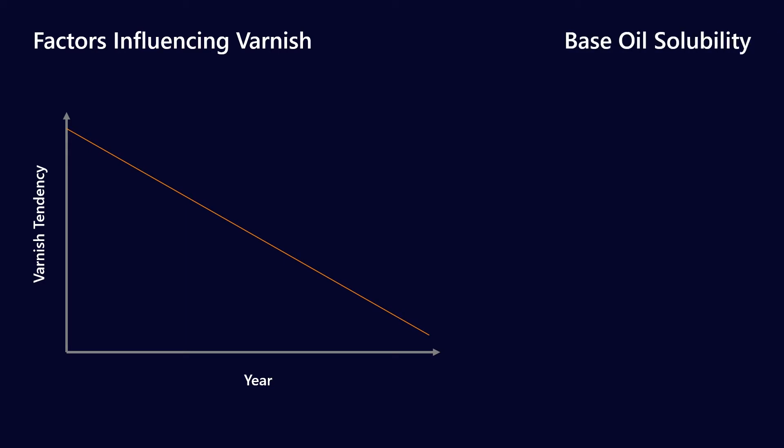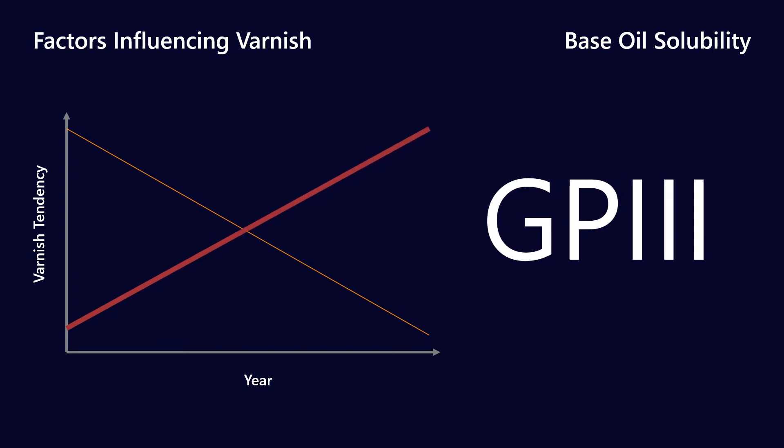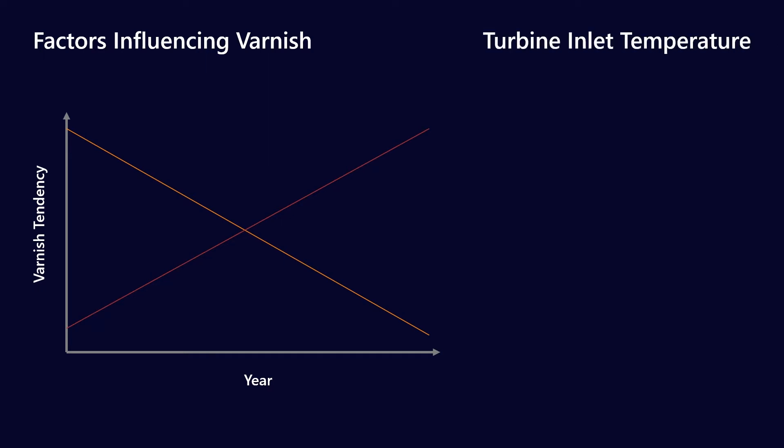However, as you change the base oil, you're also affecting base oil solubility. As covered in my previous video on API base oil groups, as you move from Group I to Group III you're actually reducing the solubility of the oil — particularly as you pull out some of the aromatic compounds, solubility decreases significantly. Solubility is something you need to prevent varnish: if you can hold components in solution so they never plate out, you won't have varnish. But with poor solubility, varnish precursors tend to plate out more easily, contributing to increased varnish tendency.